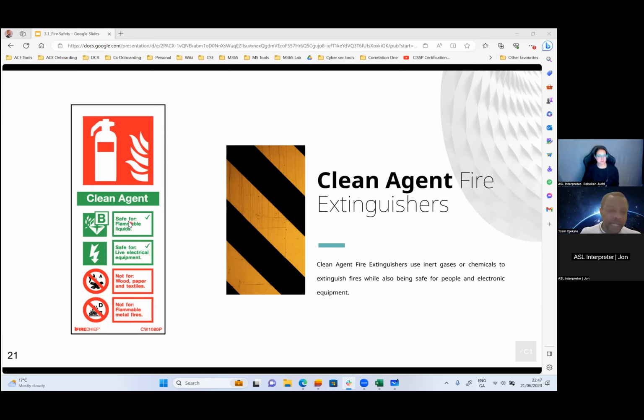So if you look at this clean agent, you see the different labels to the left. You have 'safe', and this rating shows green B, which means it is safe for flammable liquids. This one shows it's safe for live electrical equipment. The third one says not for wood, paper, and textiles, so if the fire source has any of these, don't use a suppression with this label. The final one says not for flammable metal fires. So anytime there's fire, you need to understand the source and know which of these suppressions to use. That's the reason for you to know what the labels stand for.